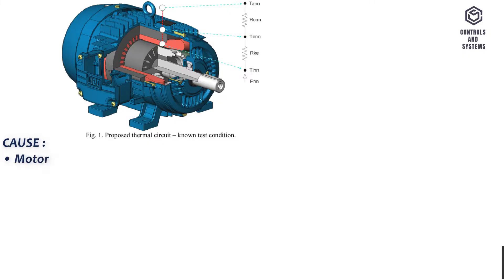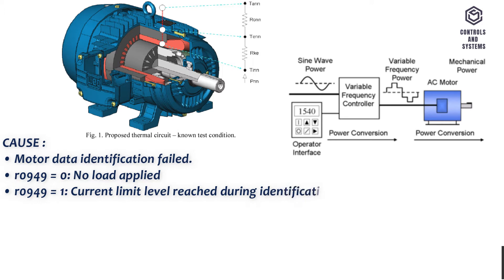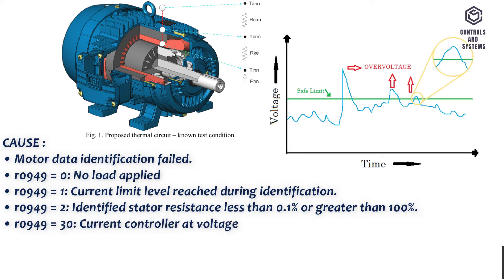Cause: Motor Data Identification Failed. R0949 equals 0: no load applied. R0949 equals 1: current limit level reached during identification.